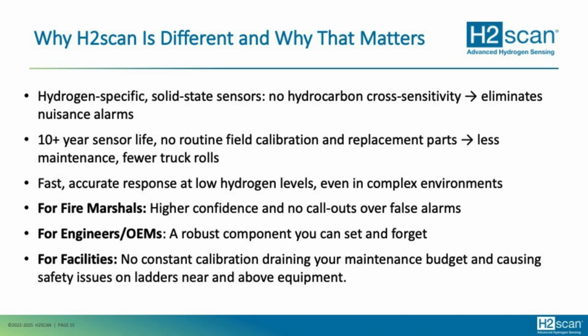It's fast, it's accurate, and you can have a lot of different things in your environment, but it will only detect the hydrogen in the air. This means for inspectors, it's a high confidence. You don't have false alarms going on that you have to respond to and log. For engineers and OEMs, it's something they can set and forget, and they don't have to worry about customers calling back to them saying this sensor is malfunctioning, or not functioning at all. So this is a very, very reliable system.